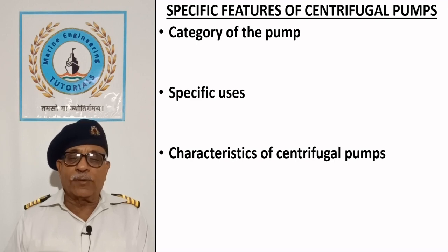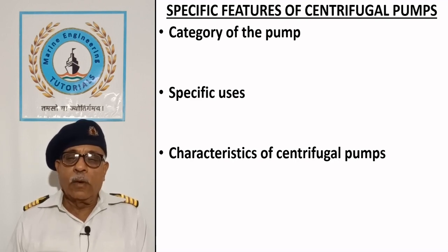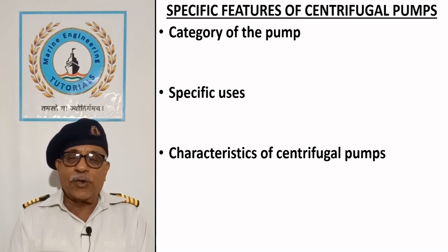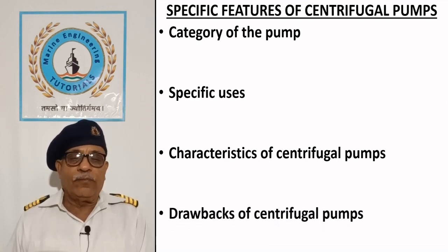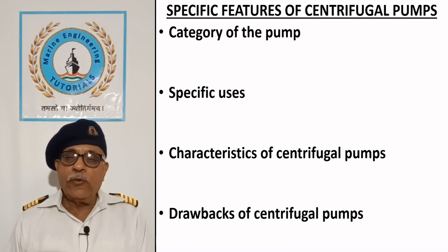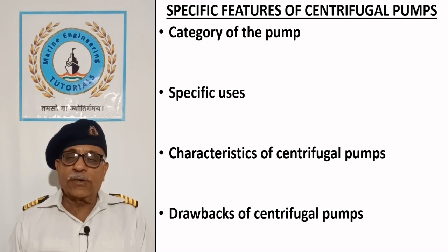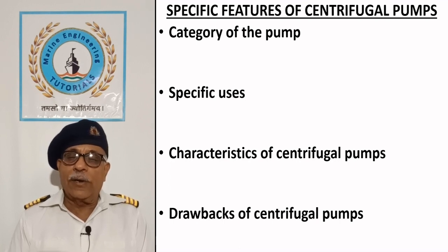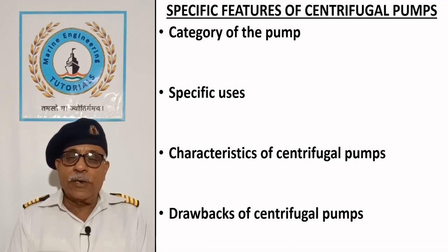Characteristics of centrifugal pumps: centrifugal pumps provide constant flow rate and discharge pressure with respect to time. Drawbacks: centrifugal pumps are unable to handle vapors. They may be equipped with a priming arrangement to remove air or vapors from the suction side when expected to draw liquids from a level below the pump, especially when the liquid is volatile in nature with high vapor pressure. This problem can be eliminated if the pump is submerged in the liquid.